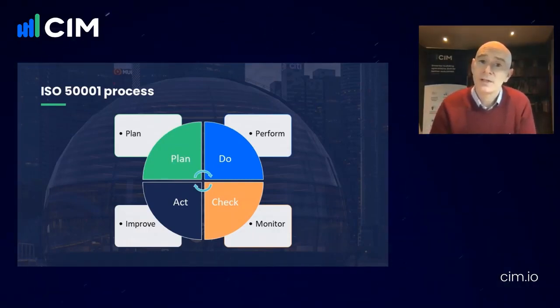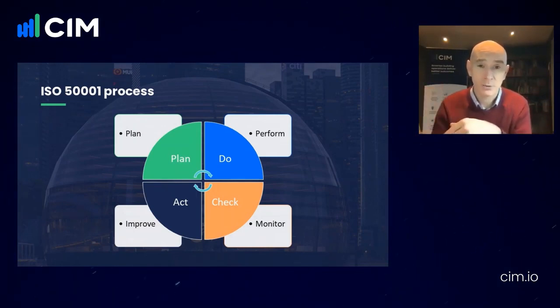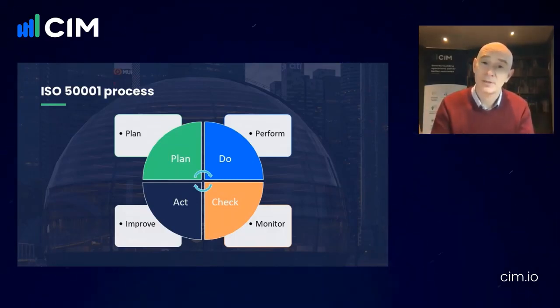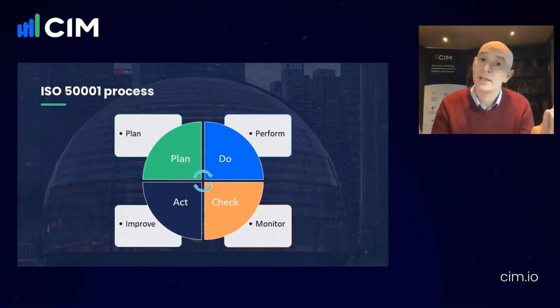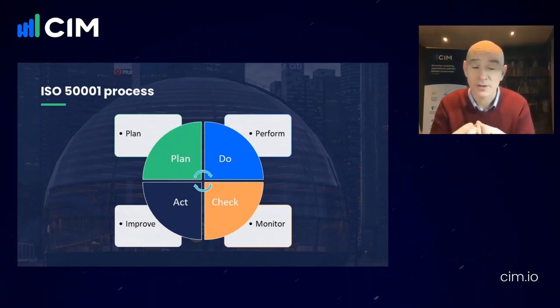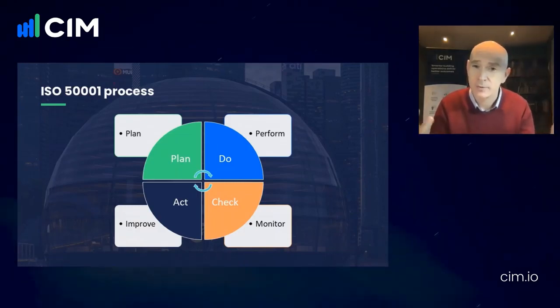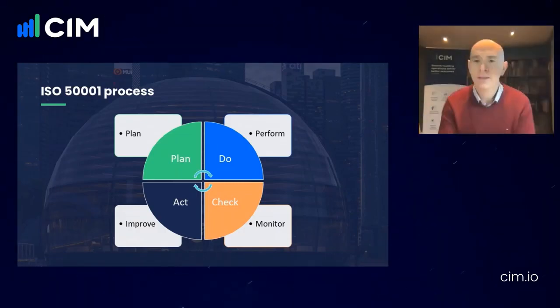On the performance side, there are energy performance indicators, called ENPIs. Once data is ingested and normalized, we put ENPIs in place to track equipment performance. This typically blends data from multiple sources, like your building management system and energy management system, to get ENPIs such as coefficient of performance on a chiller, since you need flow meter data from your BMS and energy meter data from your energy management system if you have it on site.